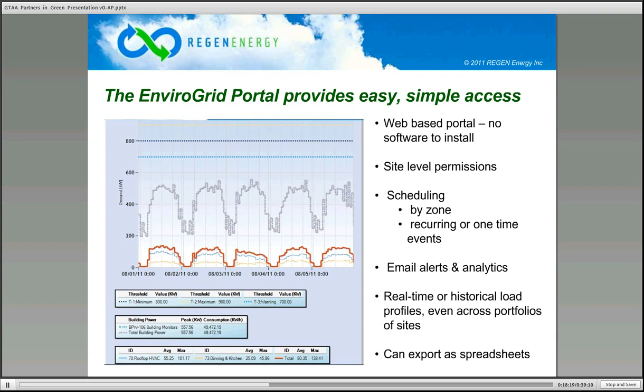The gray line that goes up and down is new this year. That's our building monitor. We put a controller on the building mains. It doesn't control anything, but it measures the consumption of the building and reports it on the same portal as all the other stuff, so you can see what's going on in the entire building, not just the loads we're controlling.